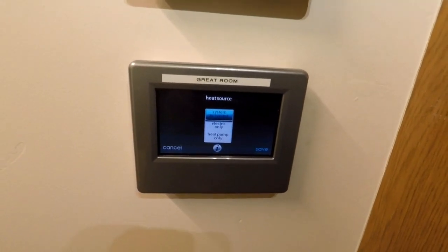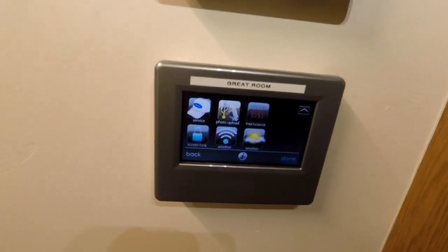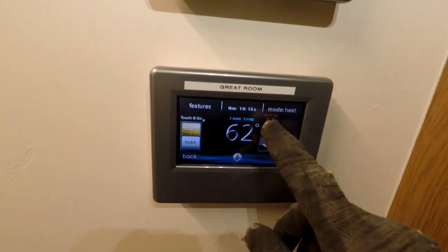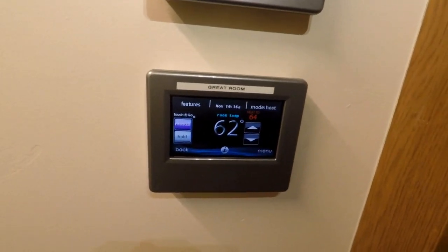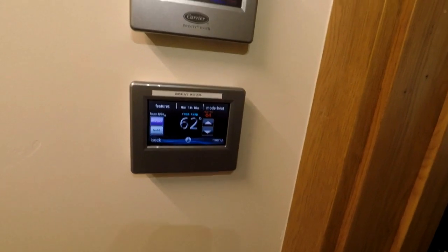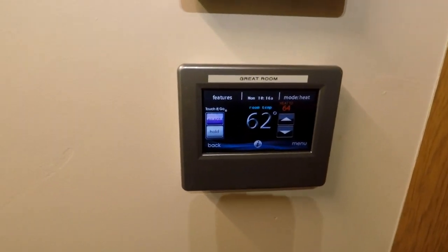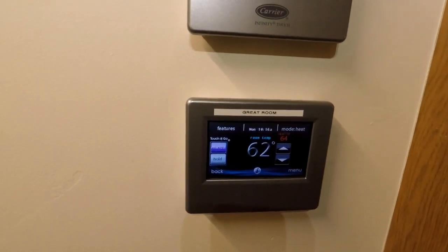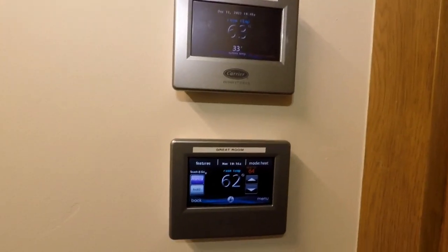You know, I don't know why the brown wire on both of them failed. That's pretty ironic, but it did. And I know on that sitting room unit, that's the second time that I've personally been out here and had a bad wire and had to change it out with a different one. I put that brown wire in last time I was here. So that's pretty crazy, man. I don't know why that is. And again, it's very ironic that it's the same color wire, but it is what it is. And that was the fix this time.